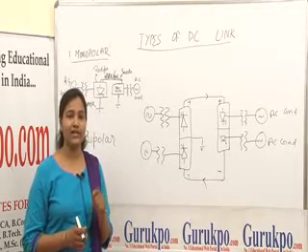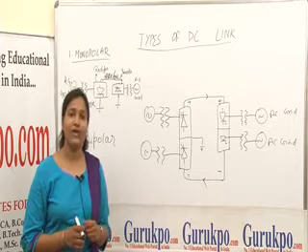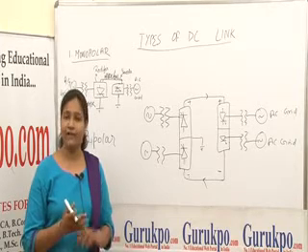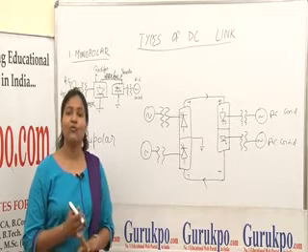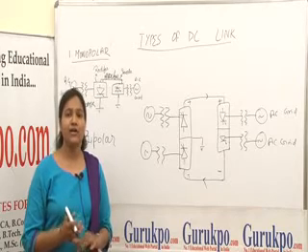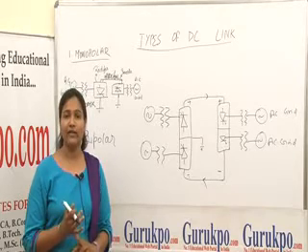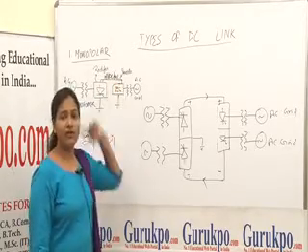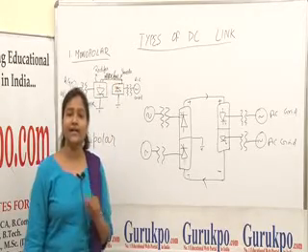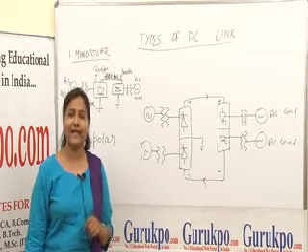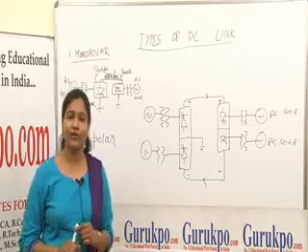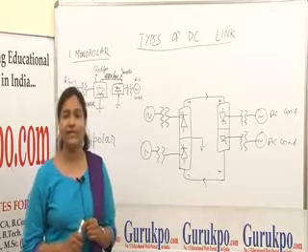Hence, if we replace the ground with a conductor of the same value, it will be very costly, ineffective, and inefficient. Whereas the ground provides a cheap and efficient method for the return. This overhead line or single conductor is generally used as negative polarity, because with negative polarity, the corona losses and radio interferences are very low.